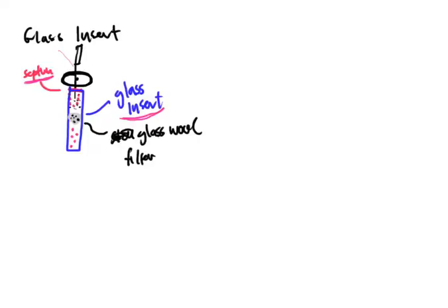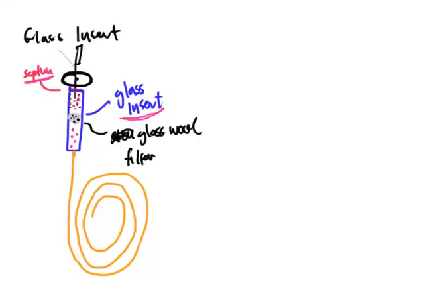The glass inserts are all made a different way. But eventually, they all will lead to the column. The column gets attached up here to the very end, and this will be the column inside of the machine. All right. So how they're made depends on the manufacturer, the method, and maybe personal preference. But the bottom line is that it's a piece of glass that has a semi-filter on it that helps take care of any trashy contaminant that will not become volatile, that will just stay lodged behind in the glass insert so it doesn't get injected onto your machine.